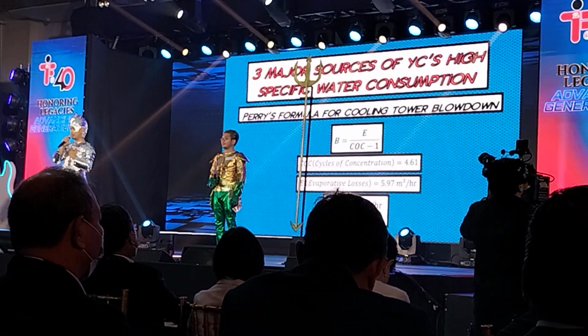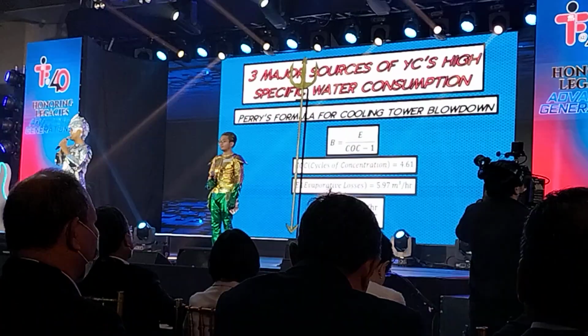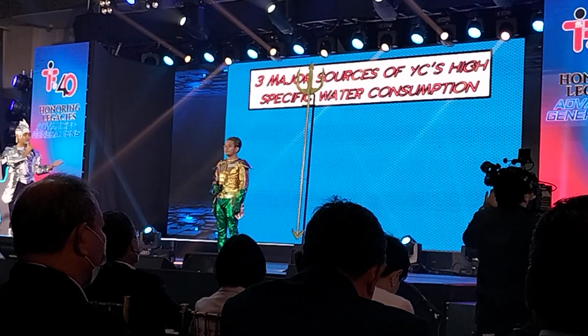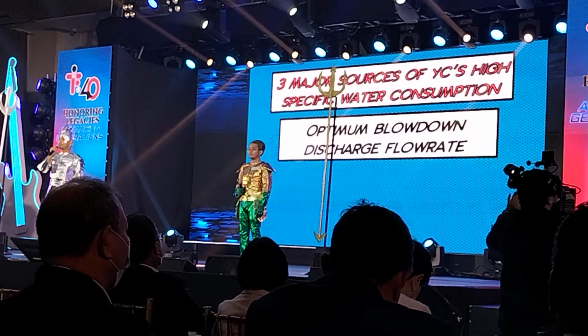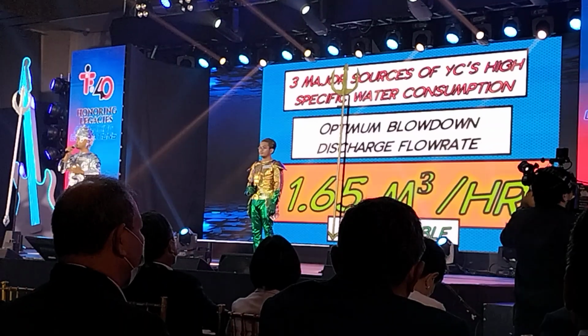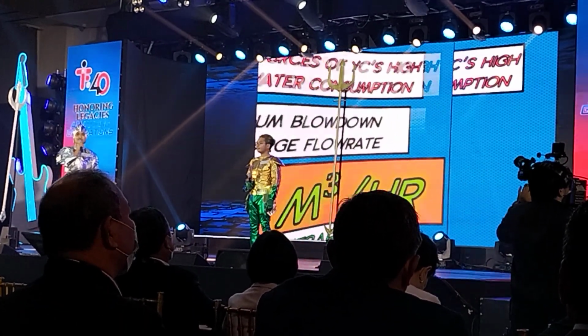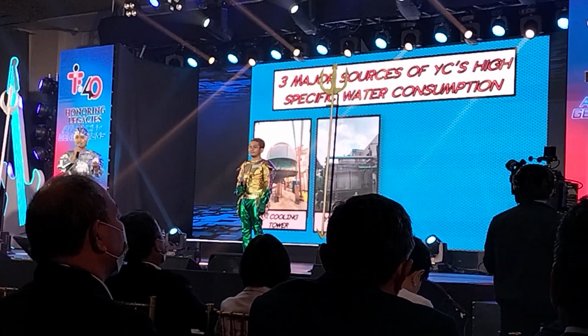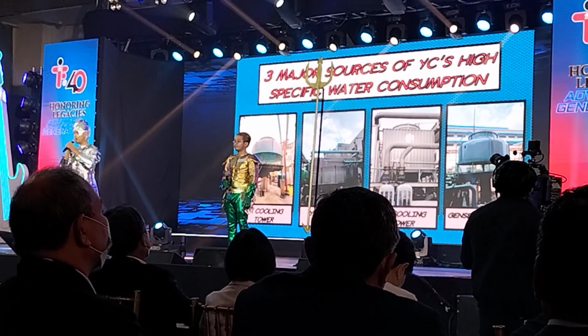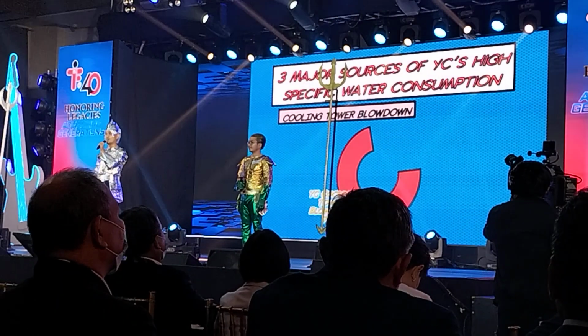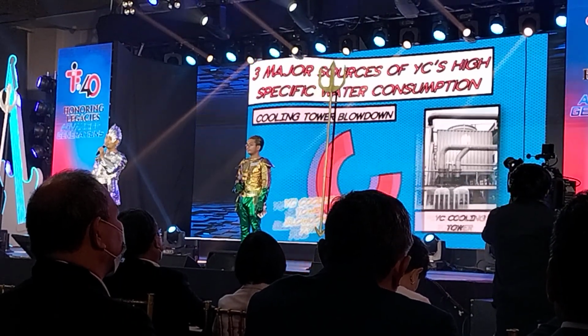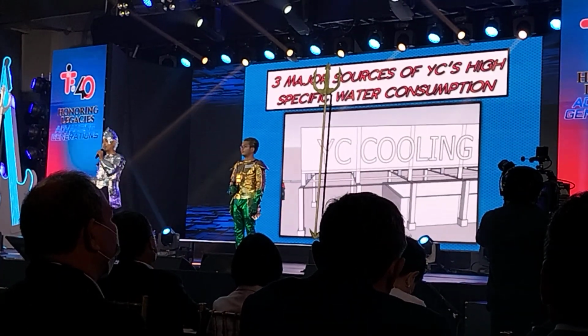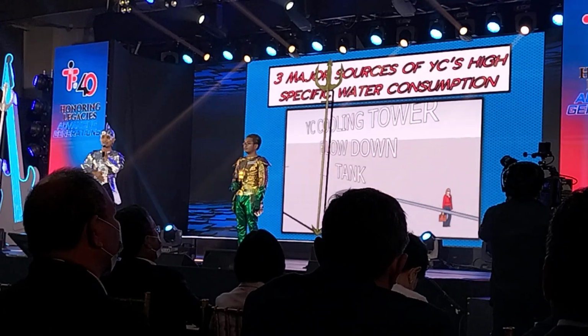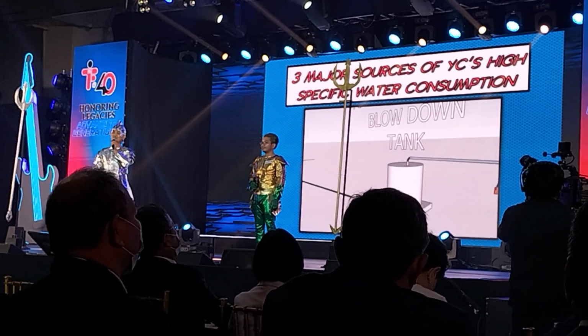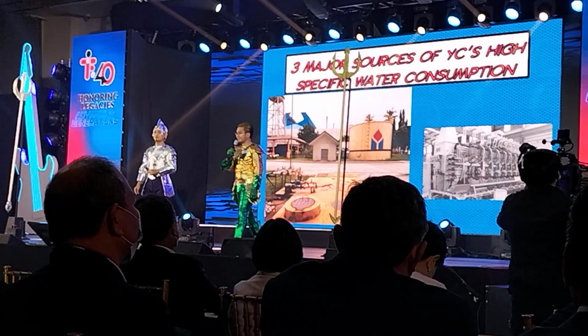Using our equipment specifications and Perry's formula from the Chemical Engineering Handbook, we deduce an optimum blowdown discharge flow rate of 1.65 cubic meter per hour. And as we further review the cooling tower blowdown meters of YA, YB, YC, and genset cooling towers, we found out that 73% of the total blowdown losses came from the YC cooling towers alone. Thus, in 2022, we installed a new pipeline connecting these blowdown discharges to the YC system, and we now harness it as a new source of recycled water.